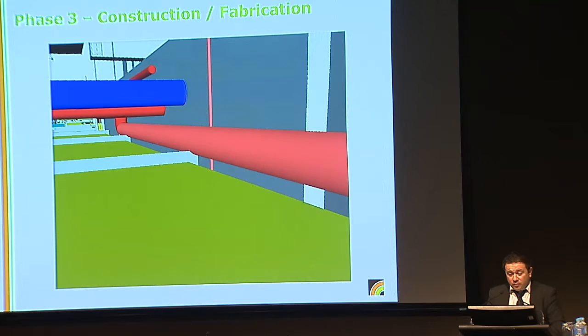The next phase is construction to fabrication, phase 3. We do our final clash detection with hangers. That's quite important; we need to ensure that's clash-free for installation. For example, here we've got a fire pipe which is located above our duct, and you can see the hanger going straight through that. You can also see that the fire pipe is hitting the frame.